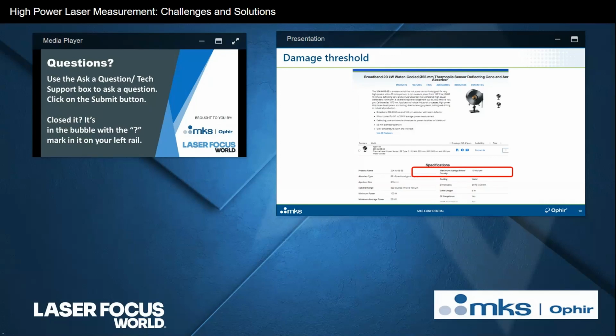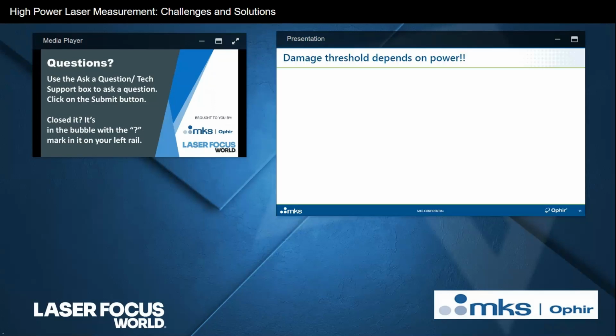I should mention that in Ophir data sheets we always recommend having a safety margin in place. There are always tolerances in the laser, in the sensor, and so on. So our recommendation is always to try and stay below 50% of any given sensor's specified damage threshold as a safety margin.